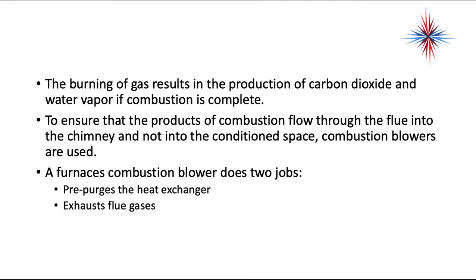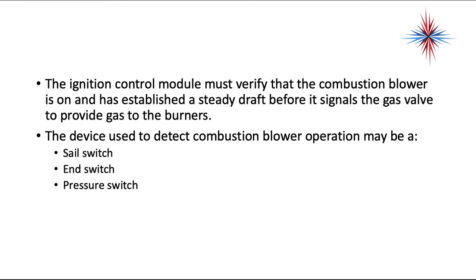A furnace's combustion blower does two jobs. First, it pre-purges the heat exchanger — it gets all unburned combustible gases out of the heat exchanger prior to ignition. And then it also exhausts the flue gases, providing a flow of the products of combustion through the heat exchanger at an exact rate.